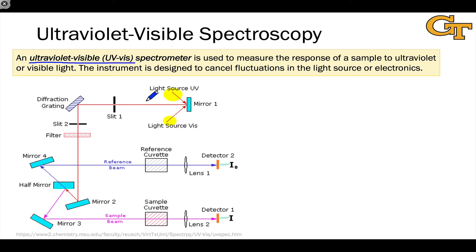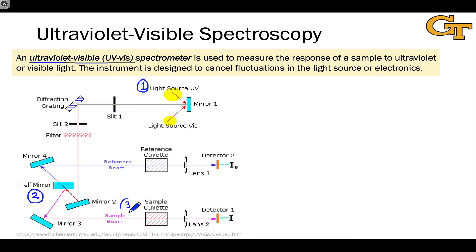Working through this diagram of an ultraviolet-visible spectrometer, we start at the light sources. We have separate sources for the ultraviolet and visible light. These are combined via mirror one into a single light source. This passes through a series of slits and a diffraction grating to select a particular wavelength of light. At point two, we reach a beam splitter, which divides the light into the reference beam — going through a reference cuvette, through a lens, and hitting a detector — and the sample beam, which heads through our sample, is focused by a lens, and hits a detector. We get two measurements: the reference intensity I0, and the measured intensity, which is attenuated relative to I0 as a result of absorption by the sample.